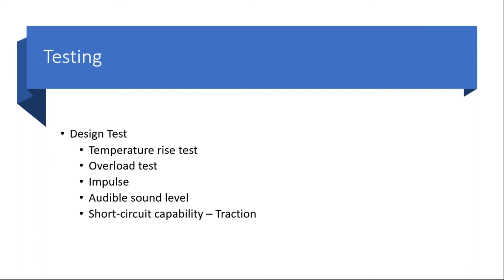But there are some customers who would like to perform this test on the actual cycle, with 2 hours at 150% and the peaks of 300% and 450%. In that case, we have to check our test room capabilities, whether it can supply that high loss for a very short time. So depending on the customer requirement, that needs to be reviewed upfront and ensured the testing requirements are met. One important thing, as I mentioned earlier, is to understand what the harmonic loss is in these transformers and ensure that it is fed during the total loss circulation.